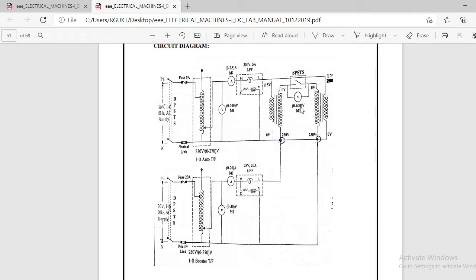So in order to check the series opposition condition, we place a switch, and across the switch we place one voltmeter. If this voltmeter shows zero reading, only then do we close the switch. After closing the switch, with the help of another autotransformer we apply the voltage in such a way that this ammeter shows the rated current. The rated current is calculated from the nameplate of the transformer. As per the nameplate, you will get nearly 6.8 amperes, so this ammeter has to show 6.8 amperes. Up to that we can vary with the help of this variac.